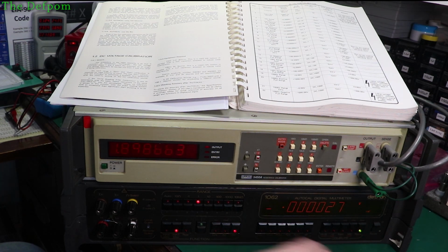Let's do it again. Being 26 counts out sounds familiar, doesn't it? For those other ranges which are out by 26 at the top end. So I don't know if this is going to do it or not. It should change each time we do a linearity check. Wait for it to finish. Come on. Must be nearly there. Must be just about there.